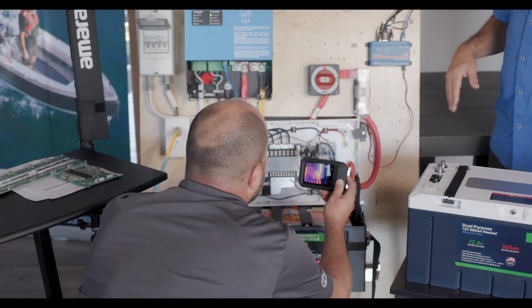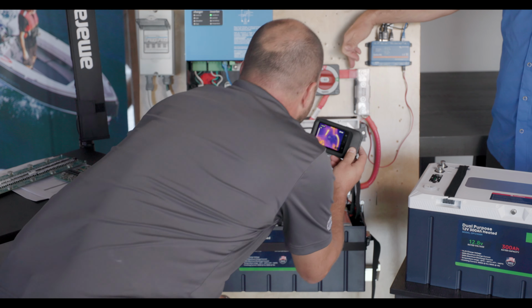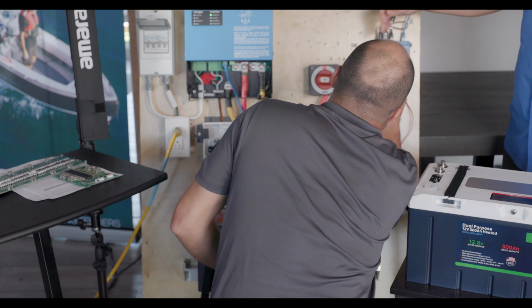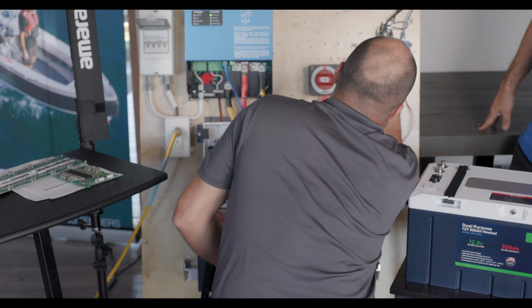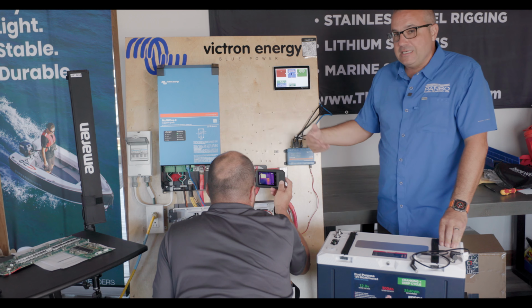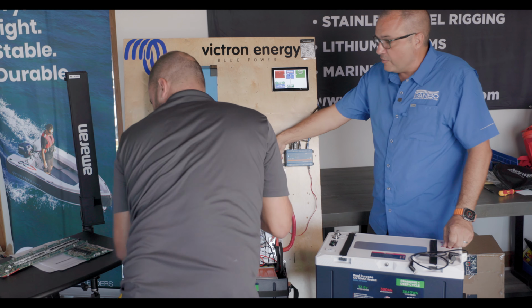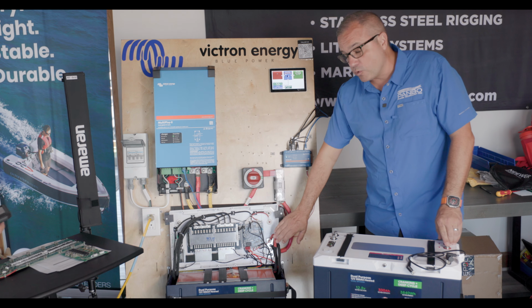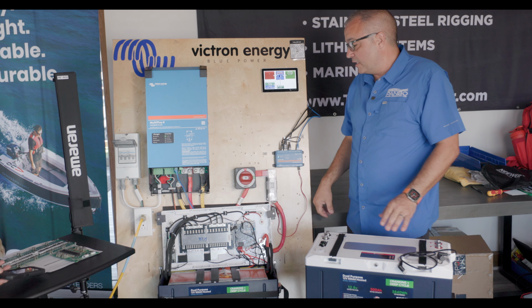I mentioned that sometimes the single points of connection get hot. We know that often our battery switches and fuse holders are the worst, especially in this case. That's 180 degrees. If we were seeing the BMS at 180, that's a little worrisome, but the BMS is a full 65 degrees cooler than the hot spot in the system. And we're keeping these terminals nice and cool because we're doubling them up as well.